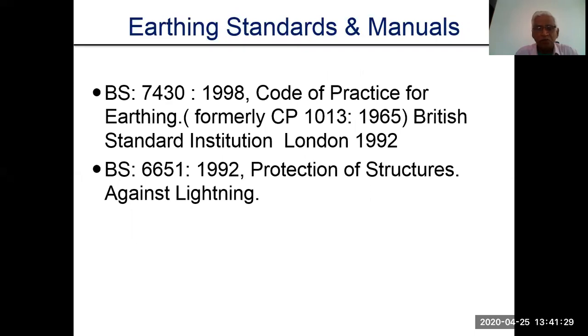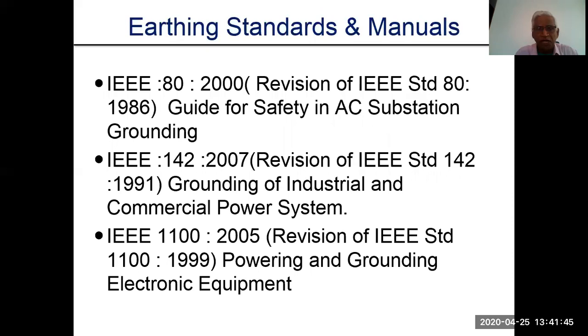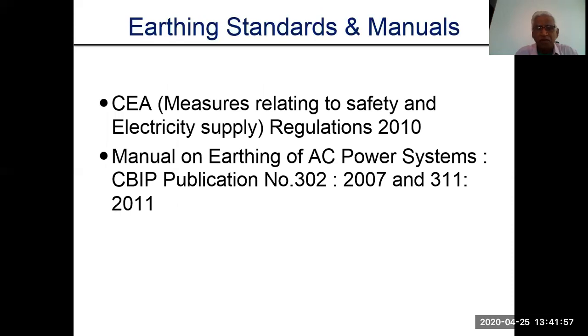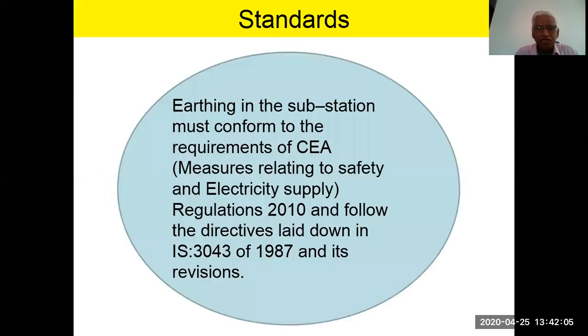Earlier it was called CP 1013, and this is made by the British Standards Institution of London, and BS 6651 of 1992, Protection of Structures Against Lightning. And further standards are IEEE 80, IEEE 142, 144, IEEE 1100 for the protection and grounding of electronic equipment. Earthing standards and the manual: CBIP has a manual on earthing of AC power systems. Earthing in substations must conform to the CEA requirements, the requirements of CEA Measures Relating to Safety and Electric Supply Regulations 2010, and follow the directives laid down in IS 3043/1987 and its revisions.